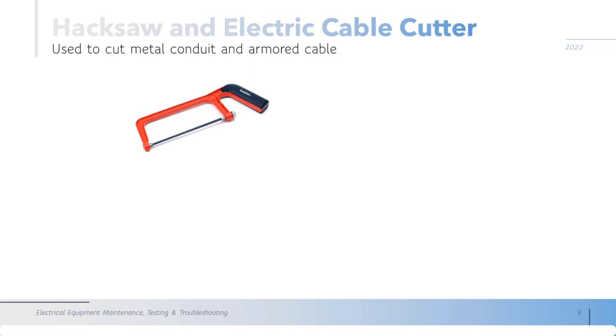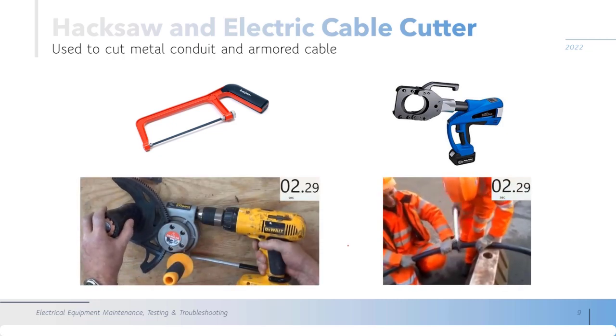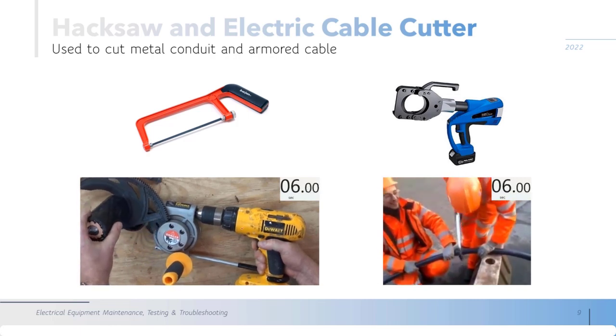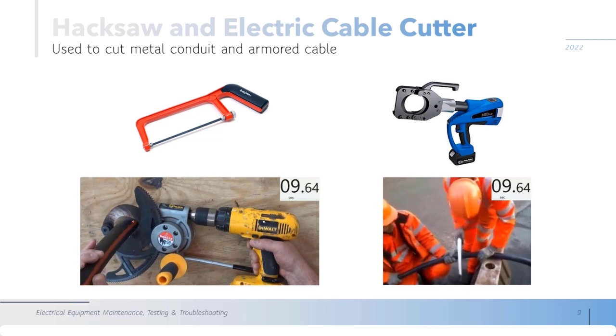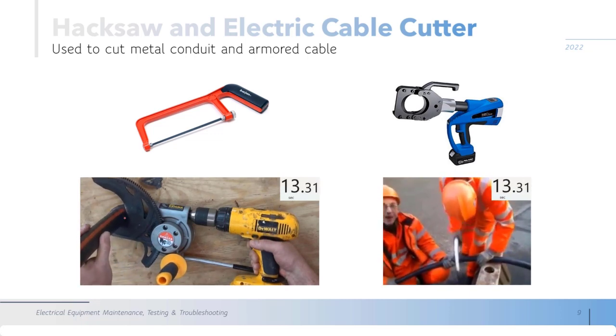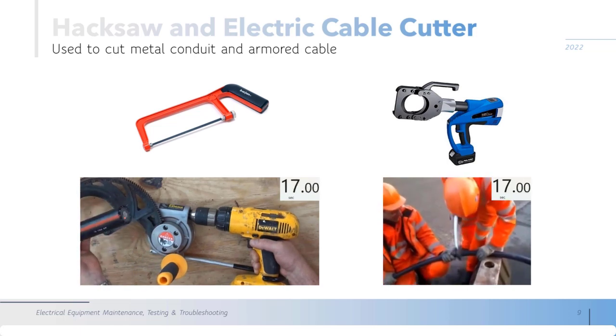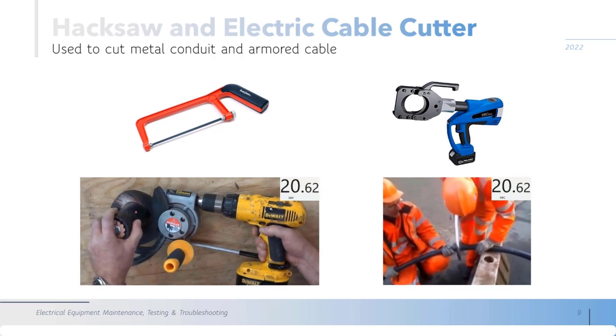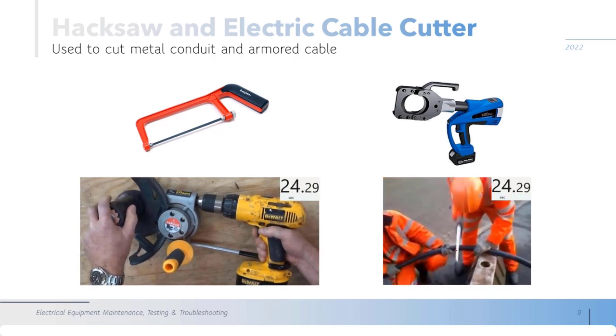So this is a manual hacksaw, and you place it on this surface and use this blade to cut the cable. And we also have an electric cable cutter, which is powered by batteries or sockets, but the one shown here is cordless. And let's see the difference between these two and the time needed to cut cables with each. So you can see here the electric cable cutter, and this is the manual. With the electric one we already cut one cable, and this is the second. So we cut the second cable, and now we are cutting the third cable, but with the manual we are still cutting the same cable.